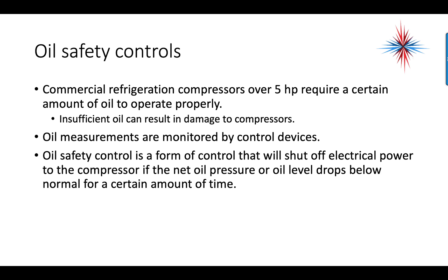Commercial refrigeration compressors over 5 horsepower require a certain amount of oil to operate properly. Insufficient oil can result in damage to the compressors; oil measurements are monitored by control devices. An oil safety control is a form of control that will shut off electrical power to the compressor if the net oil pressure or oil level drops below normal for a certain amount of time.